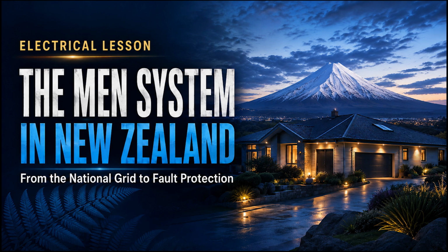If the circuit has a correctly installed and functioning RCD, the RCD uses residual current imbalance and may disconnect even though the current is too low to trip the MCB. Correct RCD protection still does not excuse a missing MEN link.